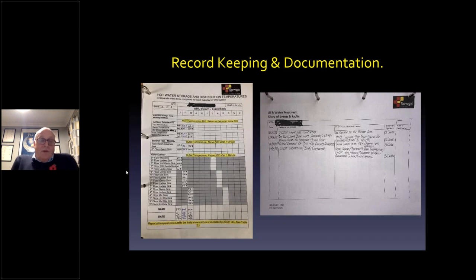A lot of people do think that, but you've got to think this is hot and cold water systems, and cold water systems and hot water systems do connect to washing machines. Your drinking fountains, which I just remembered, if they're plugged into the mains and not being used, are potentially, for all intents and purposes, a blind end. If you're not using them, they should be decommissioned, and then the pipework should be flushed. It doesn't matter whether they come out of a drinking tap or it's connected to a piece of machinery. It's the same principle.